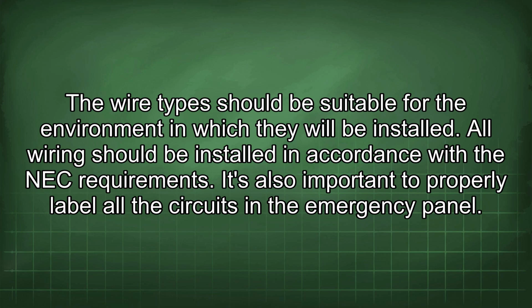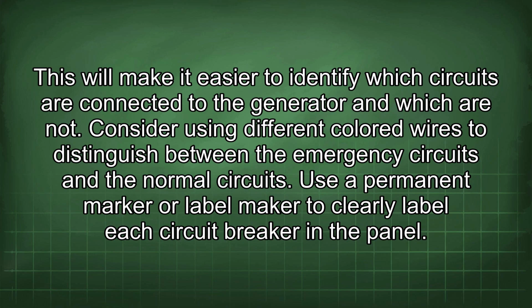It's also important to properly label all the circuits in the emergency panel. This will make it easier to identify which circuits are connected to the generator and which are not. Consider using different colored wires to distinguish between the emergency circuits and the normal circuits. Use a permanent marker or label maker to clearly label each circuit breaker in the panel.